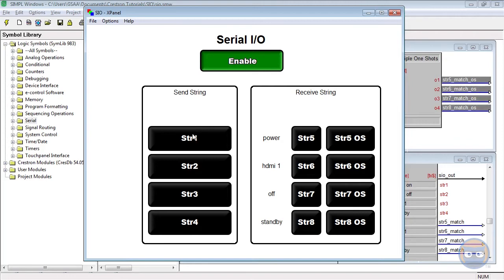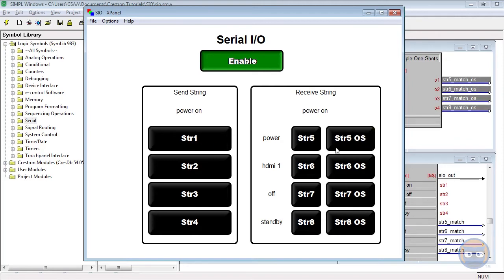When we trigger the string 1 input, the string 5 one-shot goes high for three seconds, but the S.I.O. output doesn't stay high. And that's because only the first five characters of the parameter match the transmitted string that was in parameter number one.